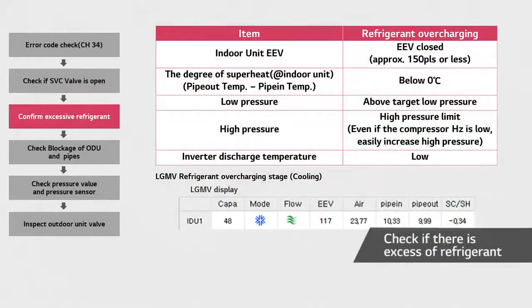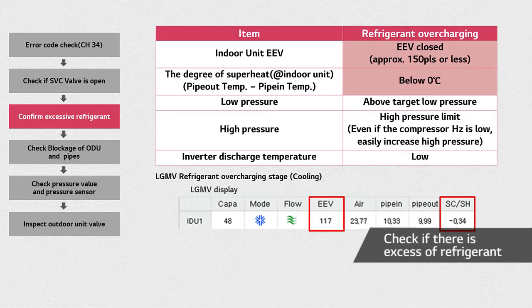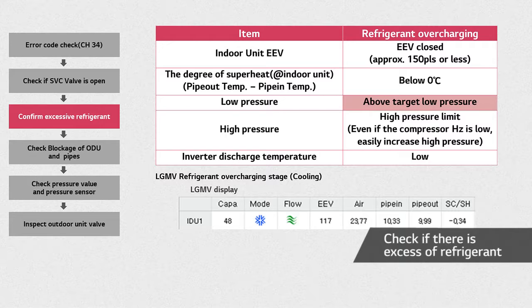You can check if there is any excess flow of refrigerant with LGMV. Once you get the ODU operating, check the cycle. You can tell there is excess refrigerant if the EEV of the IDU is narrowly closed. The superheat is below 0 degree. Superheat is a difference between the pipe out temperature and the pipe in temperature of the indoor unit. The low pressure is above the target low pressure. The high pressure level is at its limit even though the compressor's Hertz is low. And the inverter discharge temperature is low.